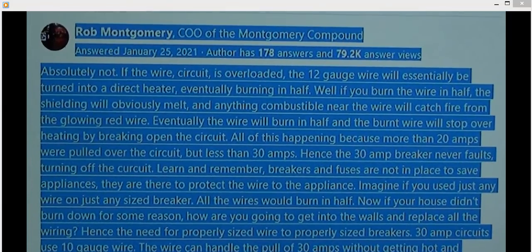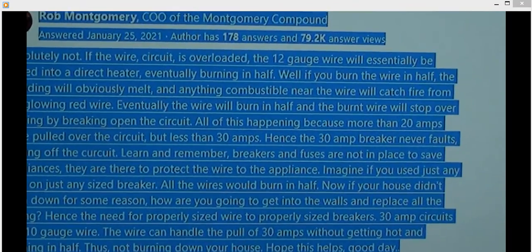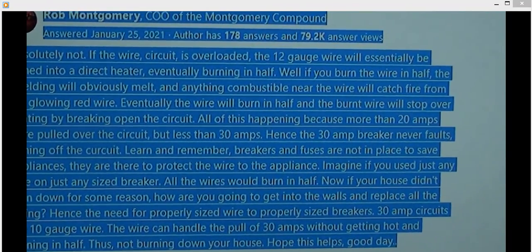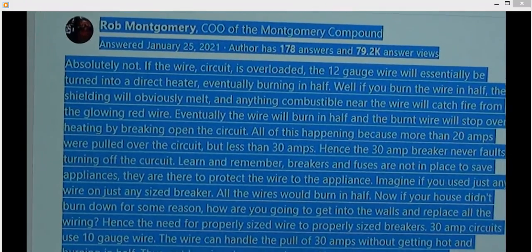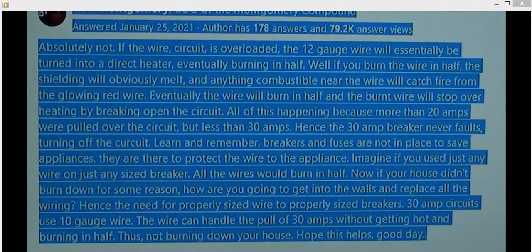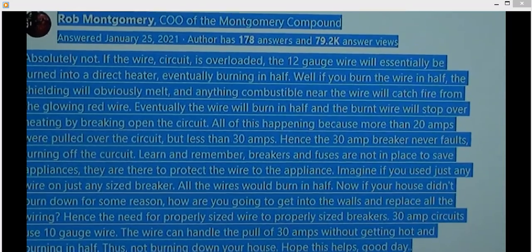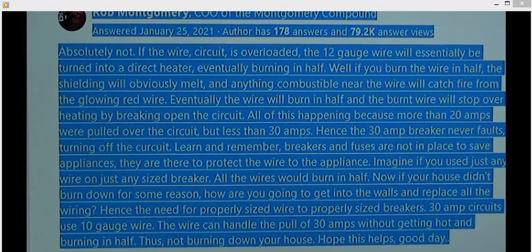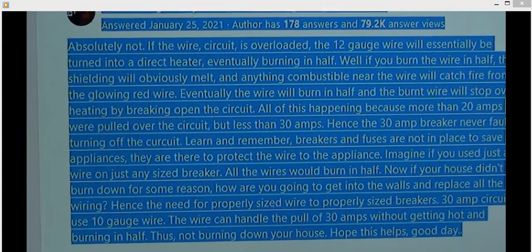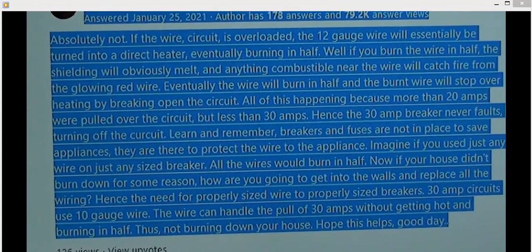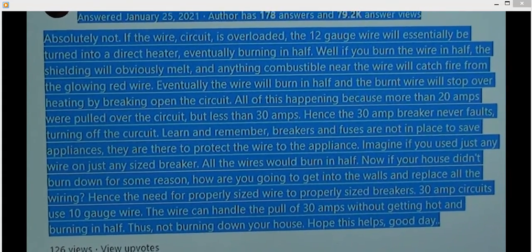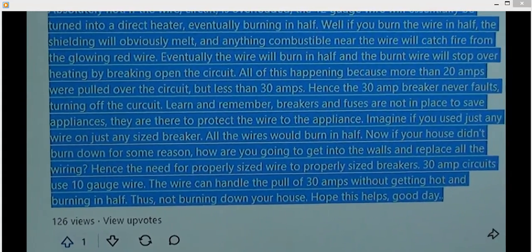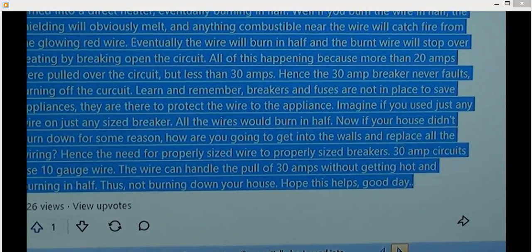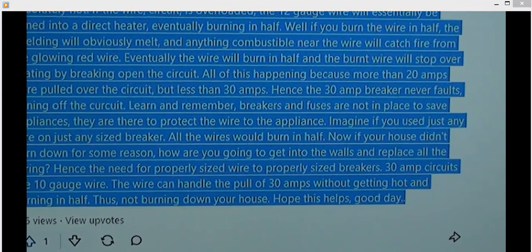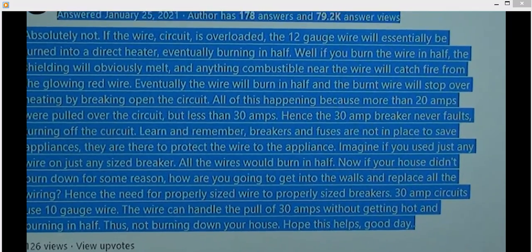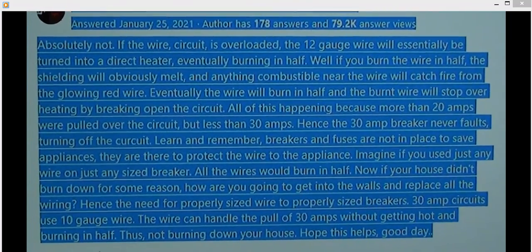eventually burning in half. Well, if you burn the wire in half, the shielding will obviously melt and everything combustible near the wire will catch fire from the glowing red wires. Eventually the wire will burn in half and the burnt wires will stop overheating by breaking open the circuit. All this happens because more than 20 amps were pulled over the circuit, but less than 30 amps. Hence, the 30 amp breaker never faults turning off the circuit breaker.